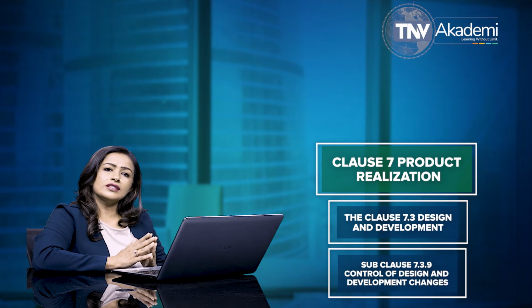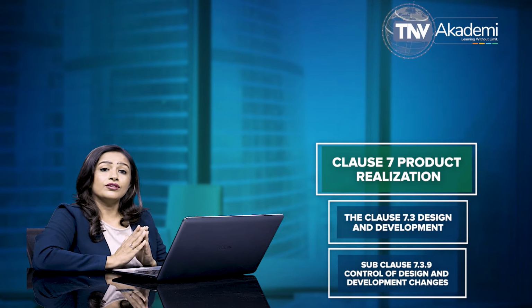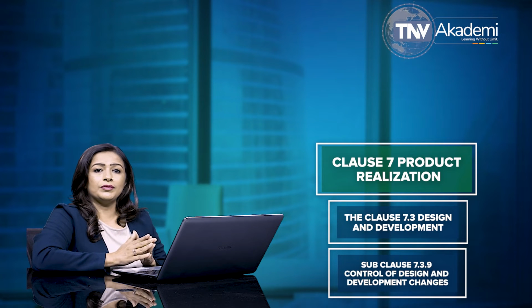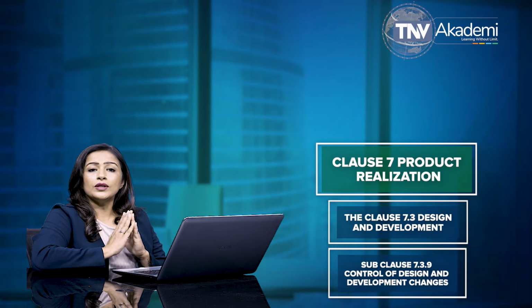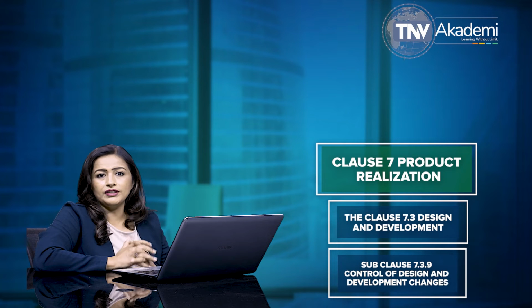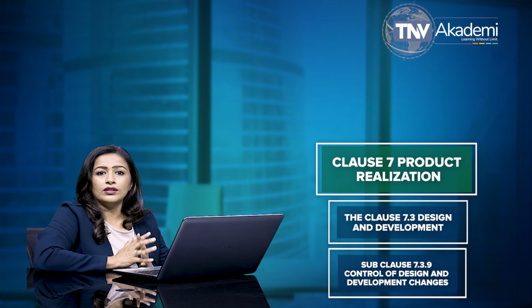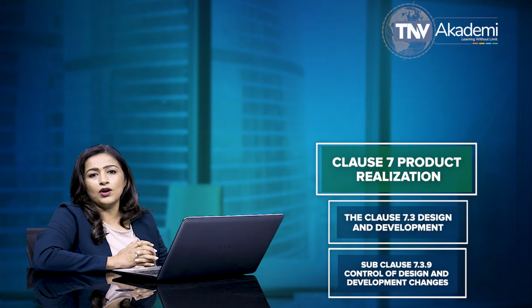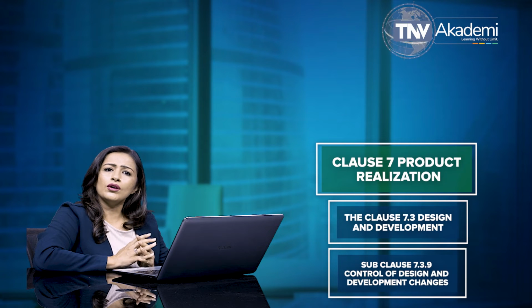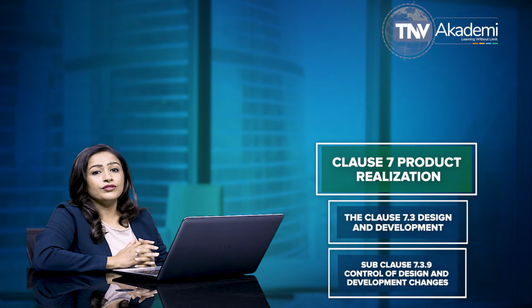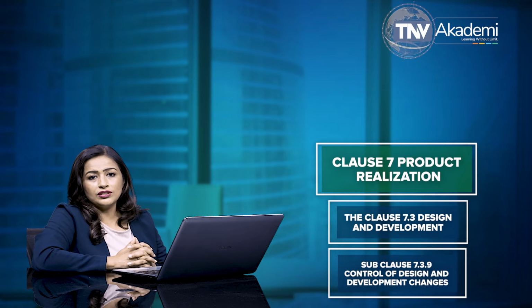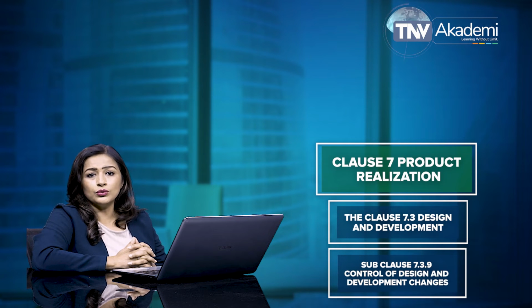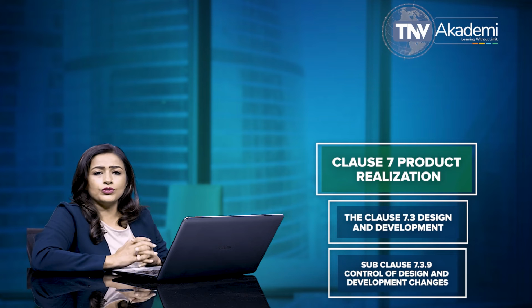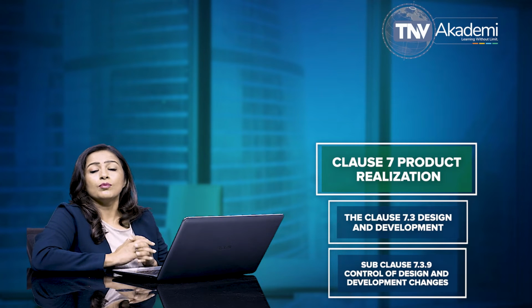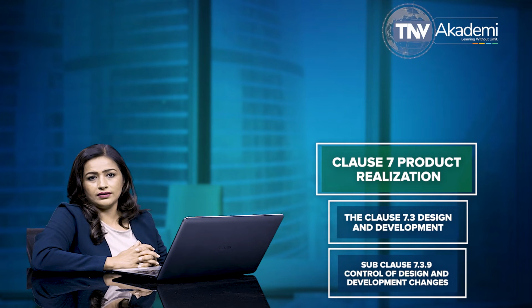According to this clause 7.3.9, the review of design and development changes is required to include evaluation of the effect of the changes on constituent parts and product in process or already delivered. The review of design and development changes is also required to include inputs or outputs of risk management and product realization processes.